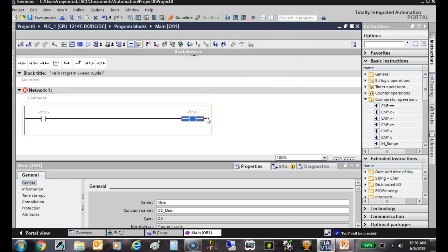And notice another thing they decided not to put over here is what? They didn't put L2. Siemens decided that we understand that it's there, right? So why put it? All our wiring is basically done between L1 and the load anyway. And since we don't have any magnetic motor starters inside the PLC, those would be outside. Then there's really no need to show L2, because there's nothing technically connected to L2 except the loads, right? Except outputs. Okay. All right. Any more questions?